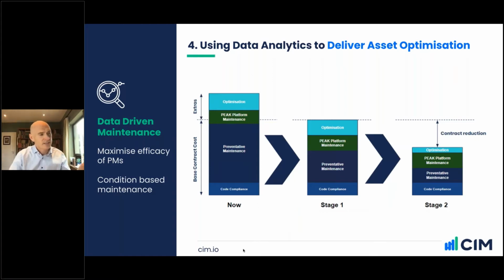What you see is sites at a current stage, and after the data analytics is deployed, it begins to inform companies as to how best they can optimize the PM routine. We see a lot of legacy issues with PM routines, where they're doing menial tasks like checking if valves are actuating or checking if LED lights are coming on in a cabinet. We even saw one PM that instructed the technician to start dusting down the top of the cabinet, and we said these are really low value add tasks for technicians to be doing.